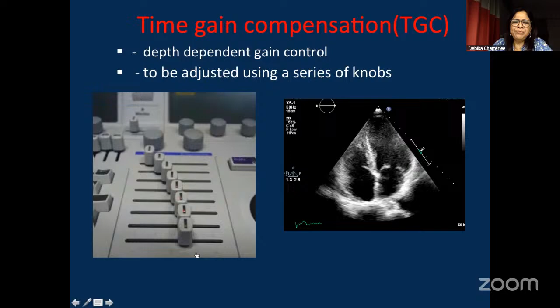Now in the imaging sector, here is the probe. This is the most anterior part of the imaging scanning sector, and this is the most posterior. So anteriorly, the ultrasound is very strong, so we need the minimum gain. So the knob is on the extreme left, whereas in the posterior aspect, as the ultrasound passes, it gets scattered, it becomes less powerful. So you need a higher gain there. So that way we adjust the TGC gain.